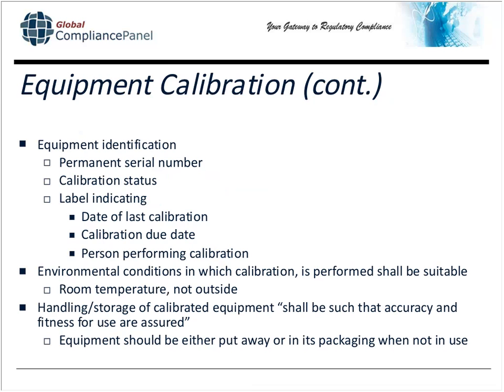On your piece of equipment, you've got to identify that piece of equipment with a permanent serial number. I've seen some etched, I've seen stickers, however you want to do it, embossed tape is fine. This facilitates identification of equipment if, and in some cases when, the calibration sticker actually falls off. So if you identify your piece of equipment in a permanent manner, it facilitates calibration. There are times when the calibration sticker comes off. It does happen. You need to account for that, because the worst feeling is to be holding a piece of equipment in your hand that has no sticker and no identification.